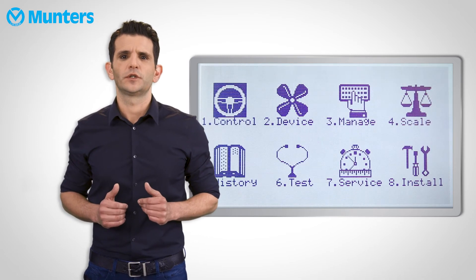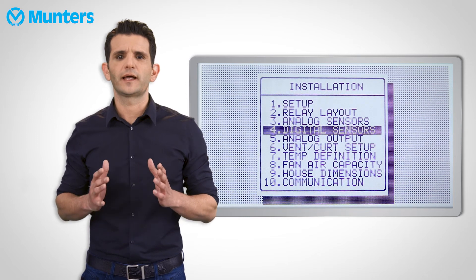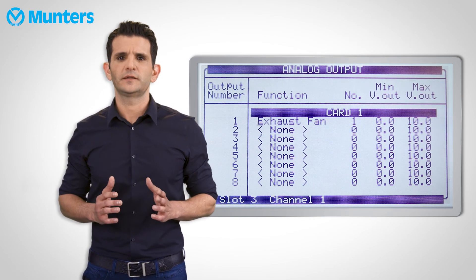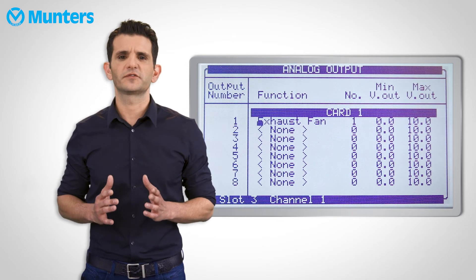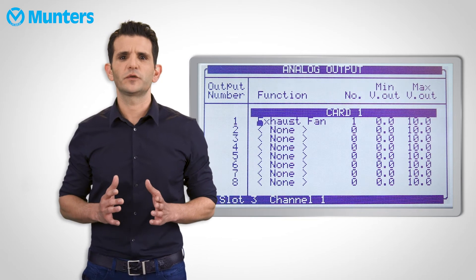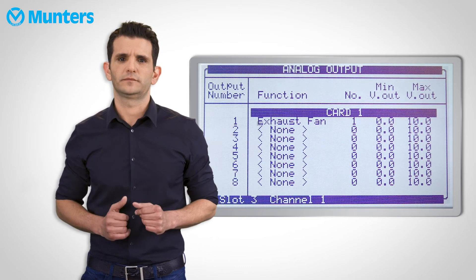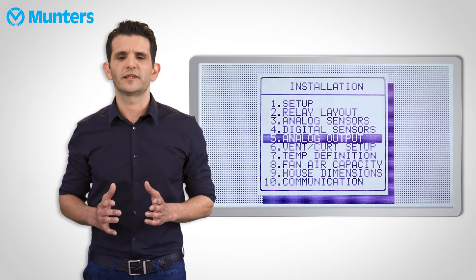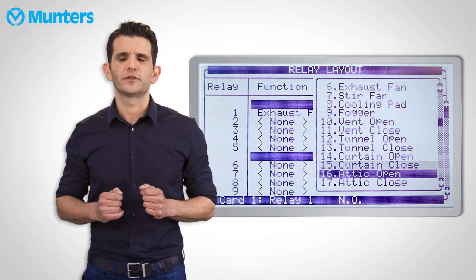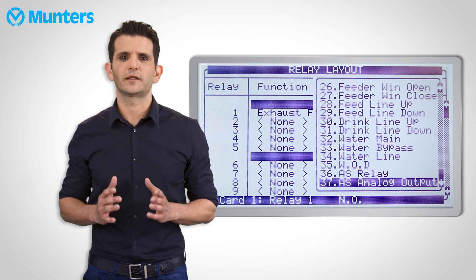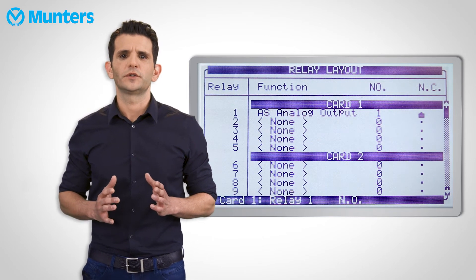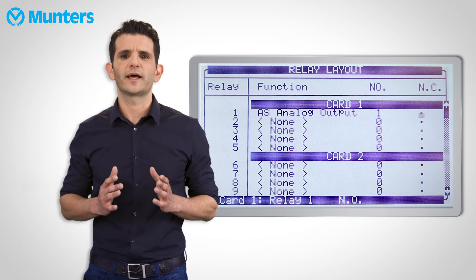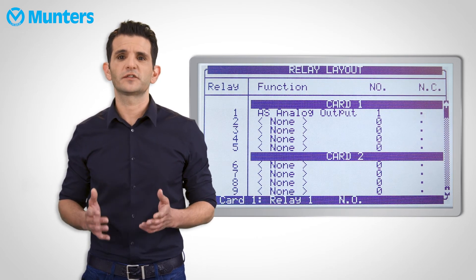So let's define a fan and assign an Analog Output Relay. First scroll to the Installation menu, and then select Analog Output. Then let's define a fan — for example, Exhaust Fan 1. As you can see on the left, this fan was defined on Analog Output 1. Now let's get out and select Relay Layout. Press Enter, and scroll all the way down to Same As Analog. After pressing Enter, you will see that the relay is now Same As Analog Output 1. Analog Output 1 is actually Exhaust Fan 1. Now, whenever the fan is operating more than 0%, the associated relay will turn on.